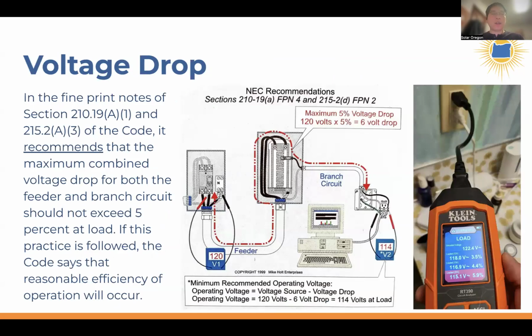Here's another important thing. It's important, but believe it or not, it's not in the National Electric Code as a requirement -- it's in there as a recommendation. The Oregon version of the electric code doesn't make any changes in terms of recommendation versus requirement. It's just buried in the code as a recommendation, and that's voltage drop.